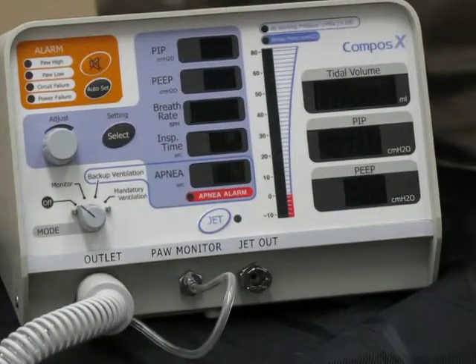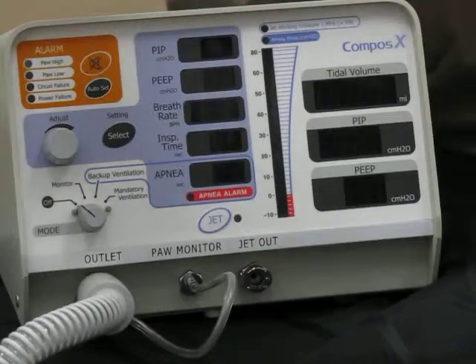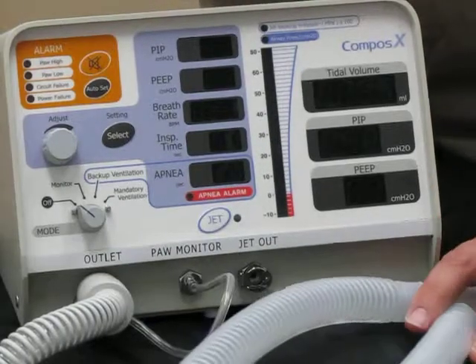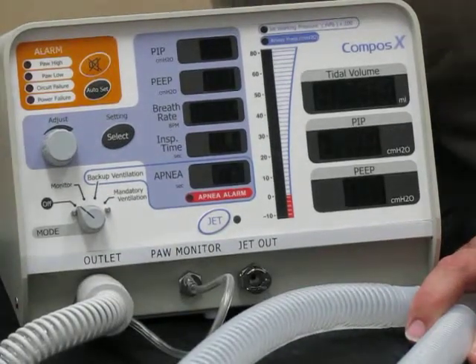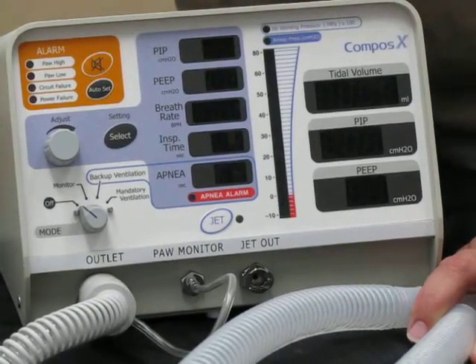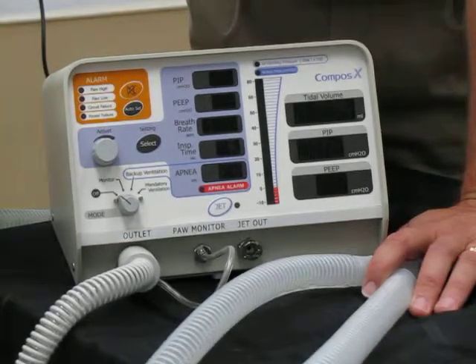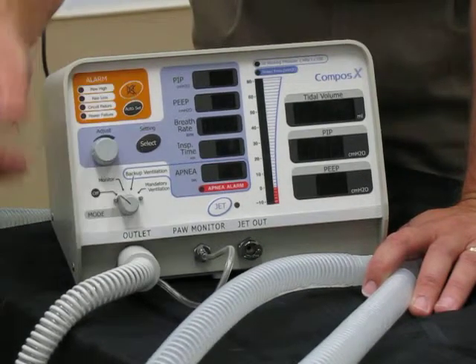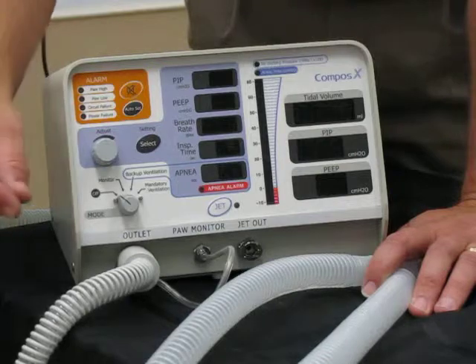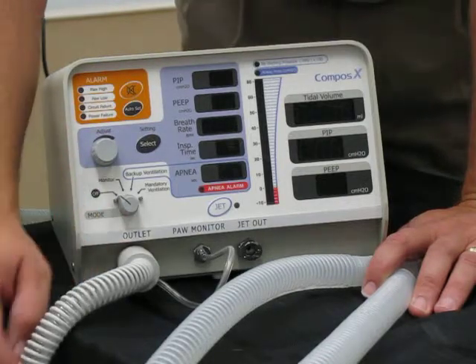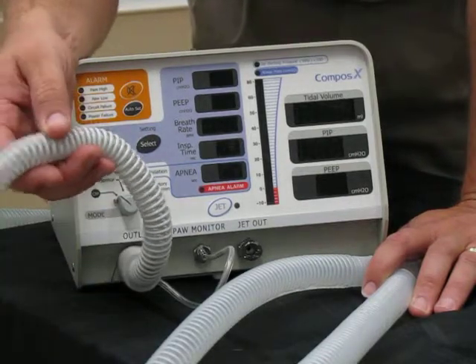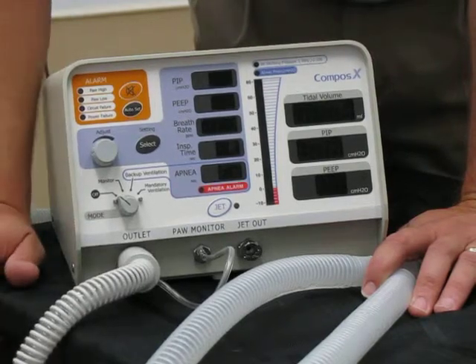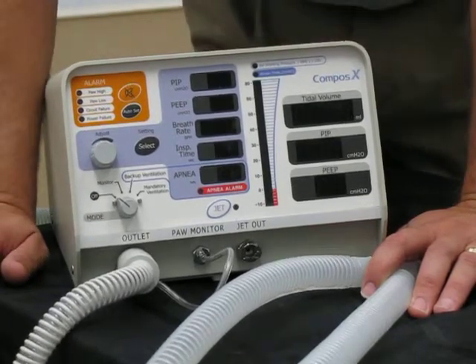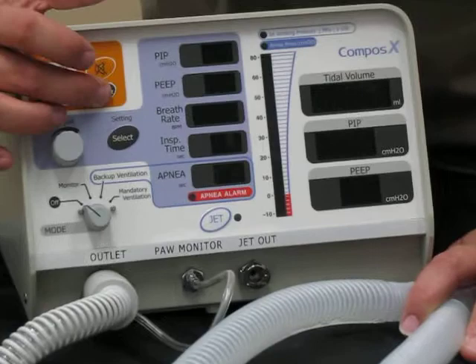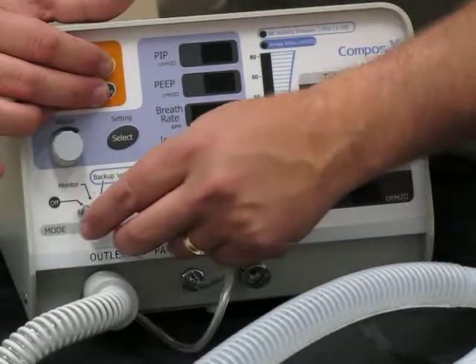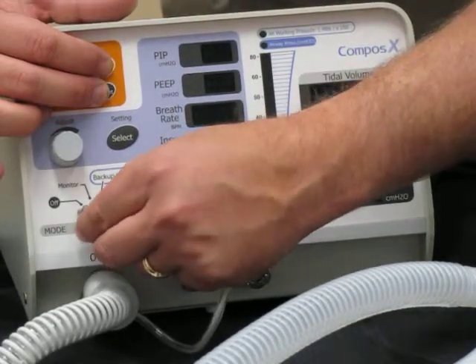You don't need to do this every time, but you do need to do it whenever you're changing the size of the circuit. So if I decide to take the adult breathing hoses off and put a pediatric circuit on, I would need to do this calibration. And if I change from one of the other 2 circuits, I would also need to do the calibration. So what we're going to do is press the auto set and the alarm button and change from off to monitor.